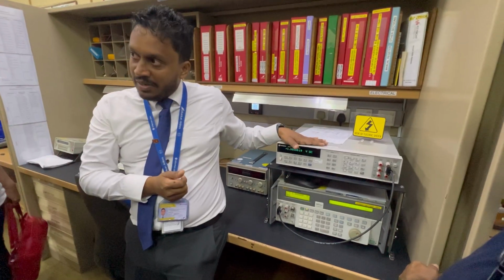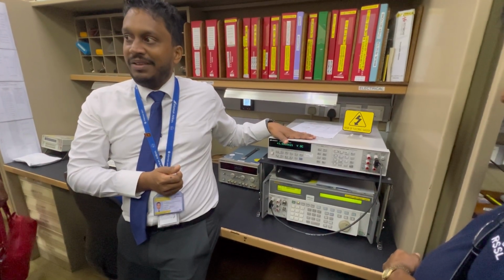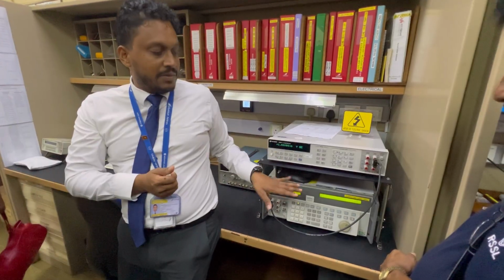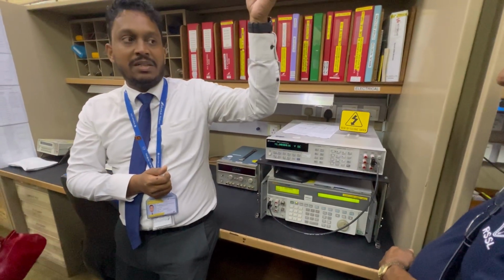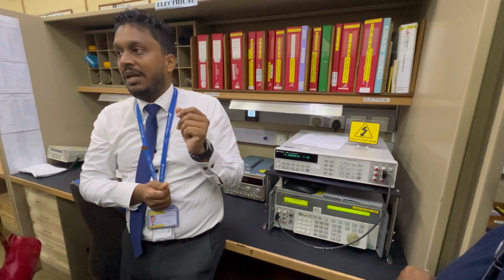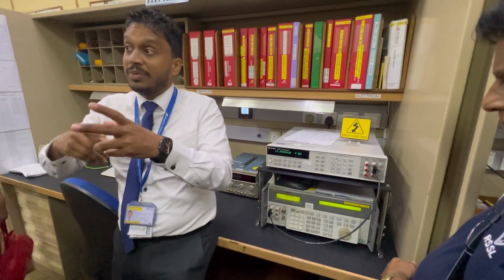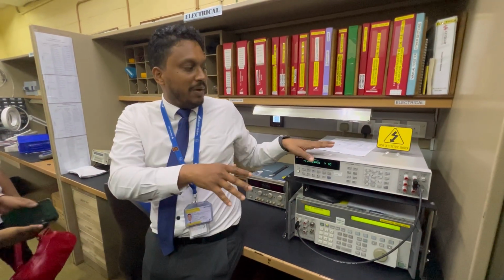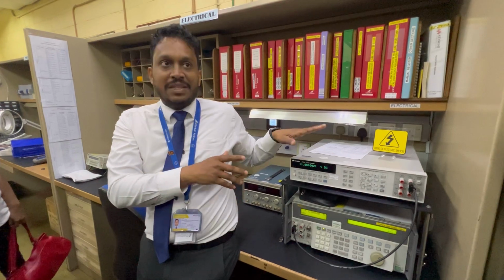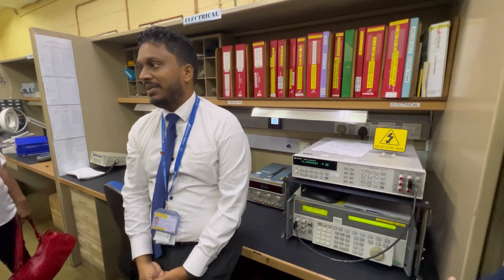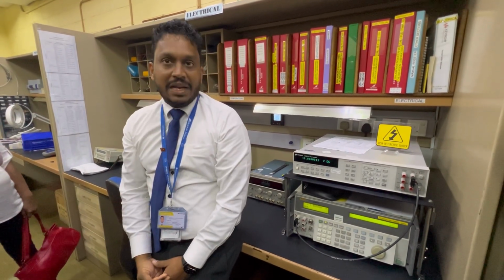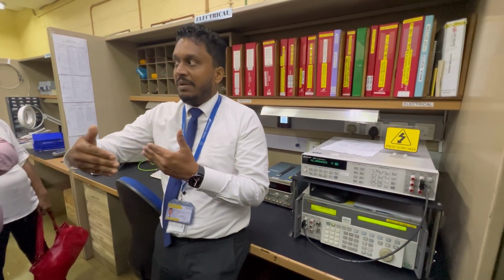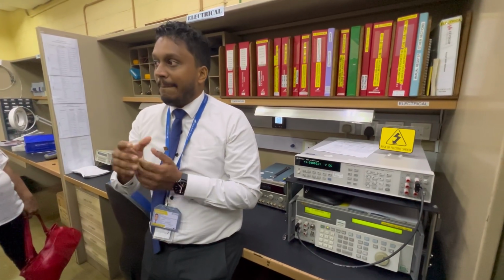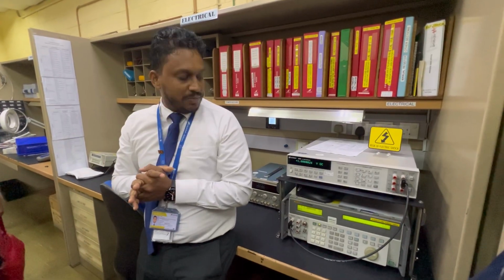But then again, we have to be very careful because this one also can drift. Right? Sometimes we send this instrument to the National Metrology Institute in Sri Lanka. Only they have such capability to measure something like that, because this is like a quality assurance, right? So we assure, because we are always monitoring it with this. If this one deviates, then there's another problem. So to eliminate that, since our calibration period is like 4 or 5 years, we have to do that kind of assurance as well.